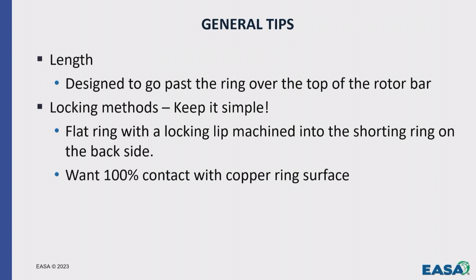General tips, the length, this is important. We see all sorts of rotors come in. Most of our rotors, we always see what's failed, so it's a great learning curve. So we constantly get rotors in where stainless steel rings have failed, but it's because they're so short. They don't either cover the ring completely, or their interference fit is wrong, or they're running out, it's the wrong material.